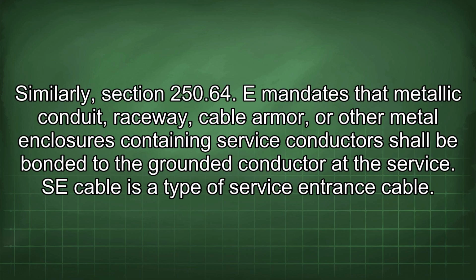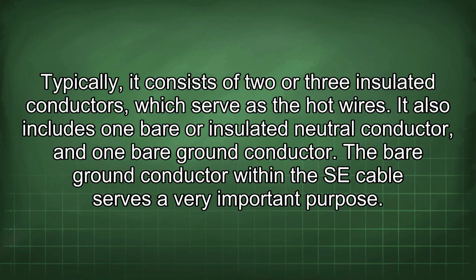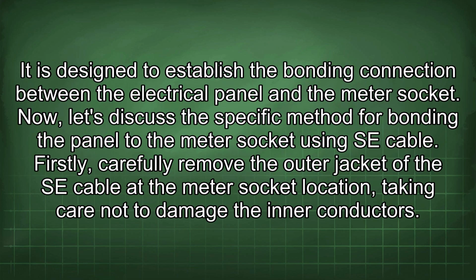Similarly, section 250.64(E) mandates that metallic conduit, raceway, cable armor, or other metal enclosures containing service conductors shall be bonded to the grounded conductor at the service. SE cable is a type of service entrance cable. Typically, it consists of 2 or 3 insulated conductors, which serve as the hot wires. It also includes one bare or insulated neutral conductor and one bare ground conductor. The bare ground conductor within the SE cable serves a very important purpose. It is designed to establish the bonding connection between the electrical panel and the meter socket.